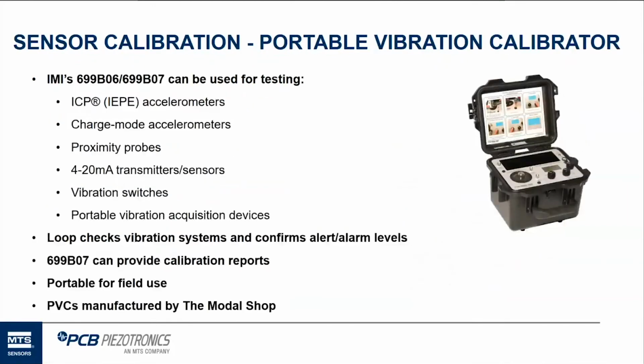Moving over to the Modal shop, we've got again the portable vibration calibrator for testing and calibrating vibration sensors: standard accelerometers, charge mode accelerometers as necessary, and proximity probes. We can check 4 to 20 sensors and transmitters. We can test vibration switches on these, and we can also send an output to a portable vibration data collector to test that device and calibrate it.